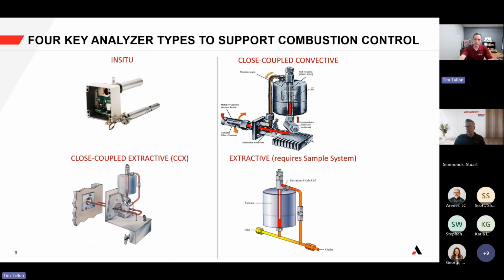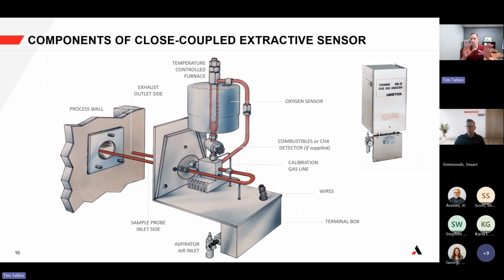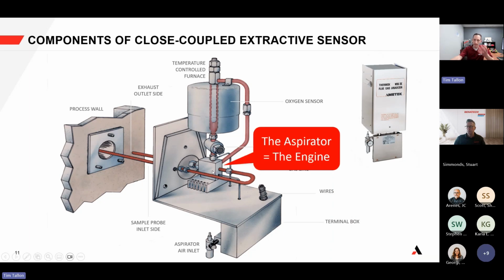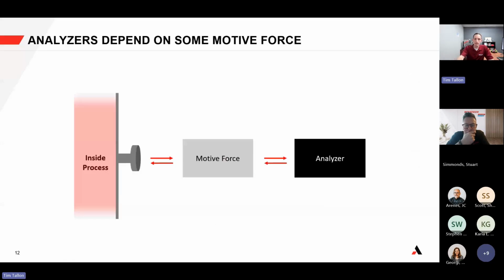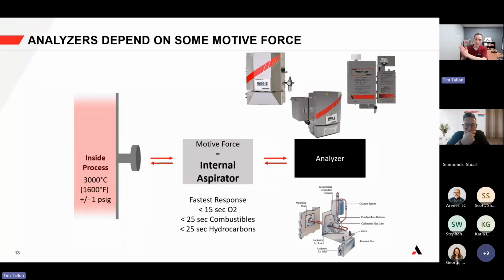And if you take the WDG-4, the predecessor to the WDG-5, in the simplest of ways, as you can see here, it has an aspirator. That aspirator is the engine that's pulling the sample in, creating the suction that's pulling a sample from the process through what we call the fast loop and right back out to process. And in the path of this, there is what we call the convective loop. This convective loop is really important because while 100% of the flow goes through the fast loop, forced through by the engine, the convective loop has about 30% of that flow. So it's a lot less sample past the detectors. As a result, it helps for reducing plugging for lower amounts of particulate. But that engine, the aspirator, is really that engine in the process. If you think about it though, connecting the process to the analyzer is that aspirator.